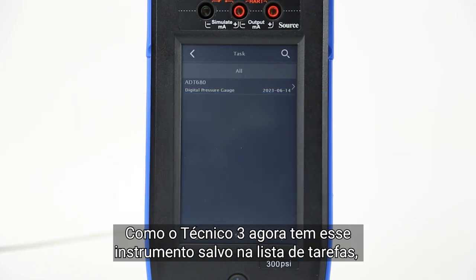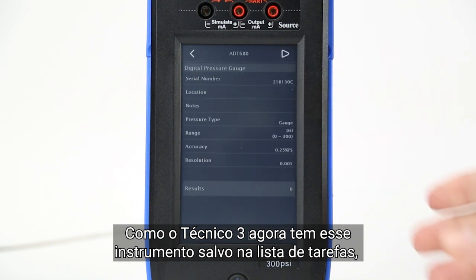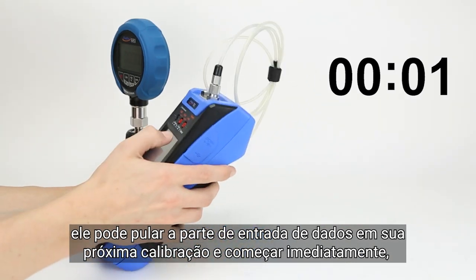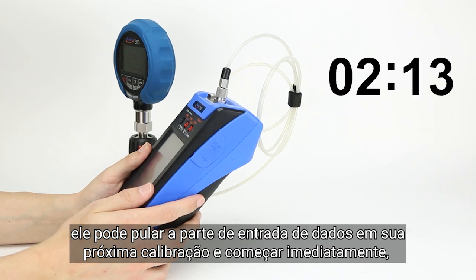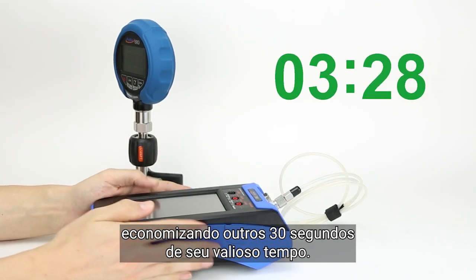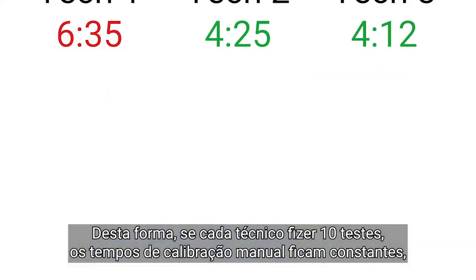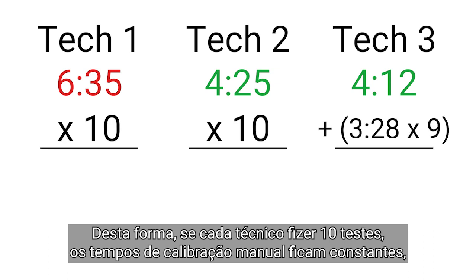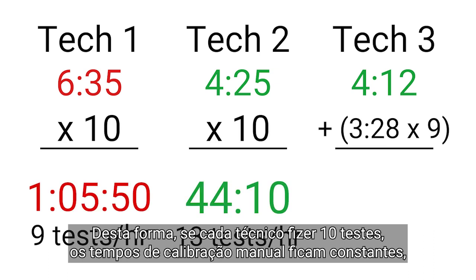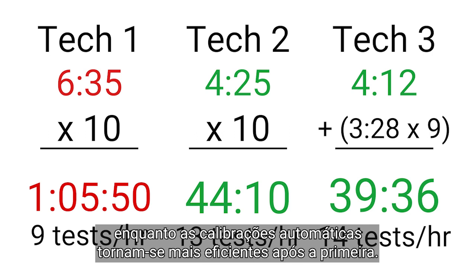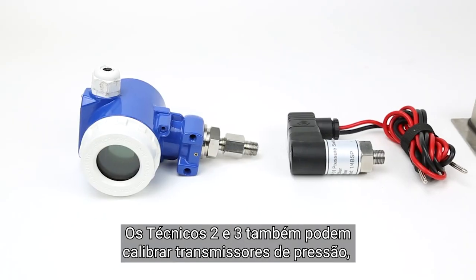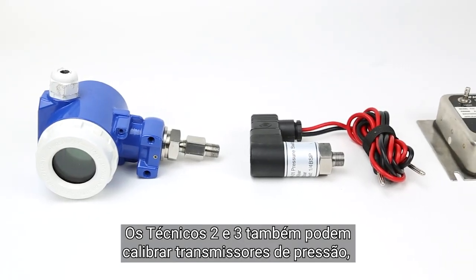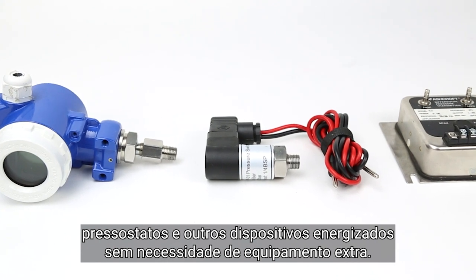But the increased efficiency doesn't stop there. Since Technician 3 now has this device saved in a task program, they can skip the data entry portion on their next calibration and start right away, saving another 30 seconds of their valuable time. This way, if each technician does 10 tests, the manual calibration times stay constant, while the automatic calibrations become more efficient after the first.